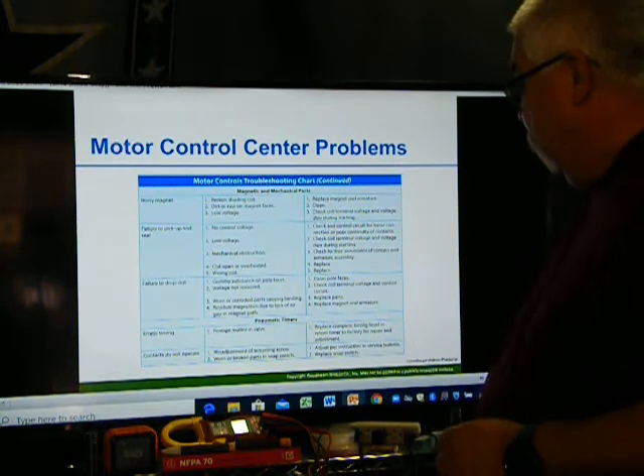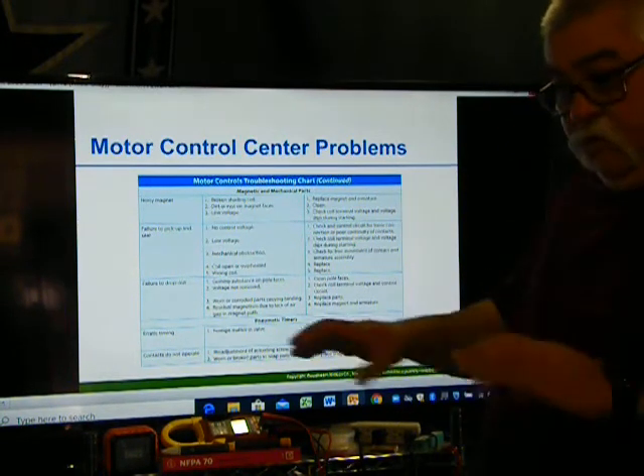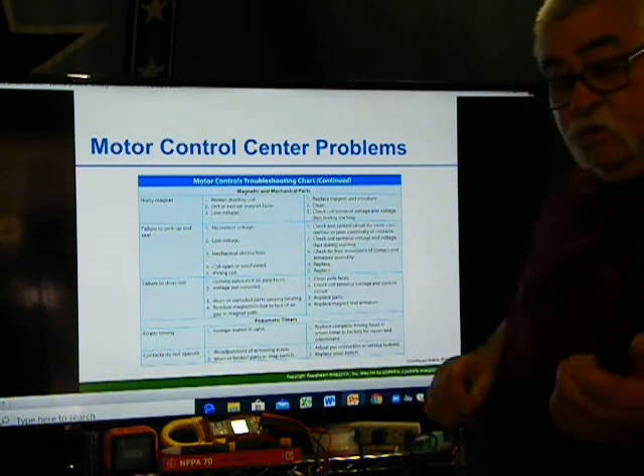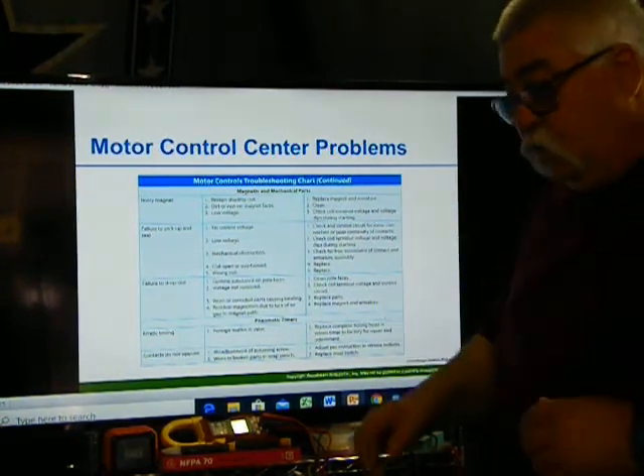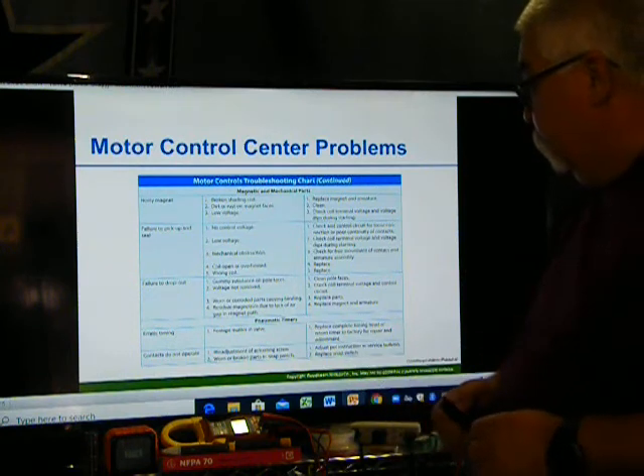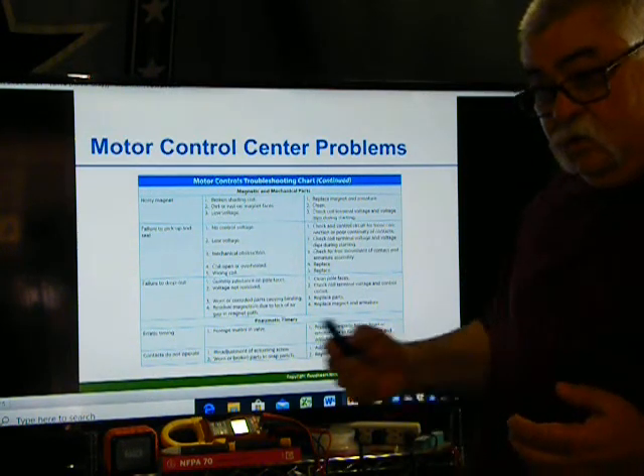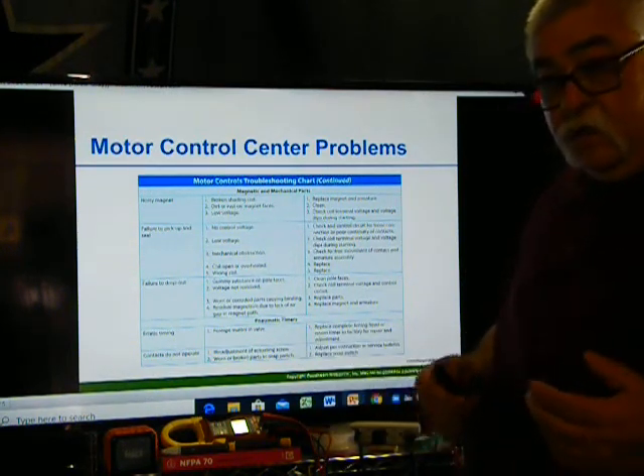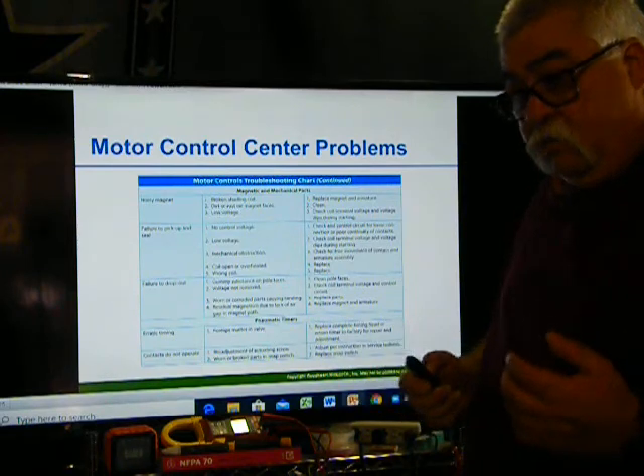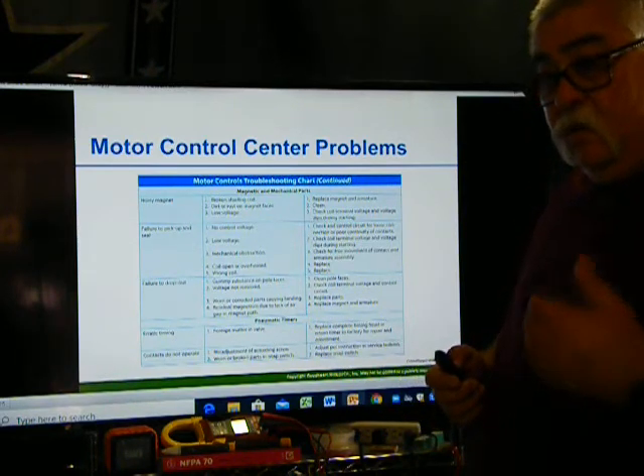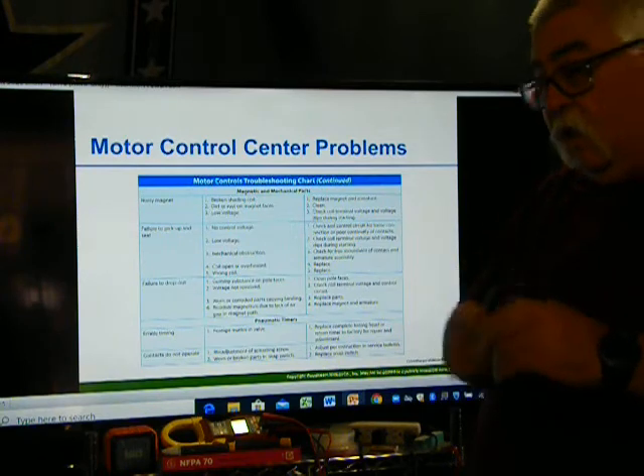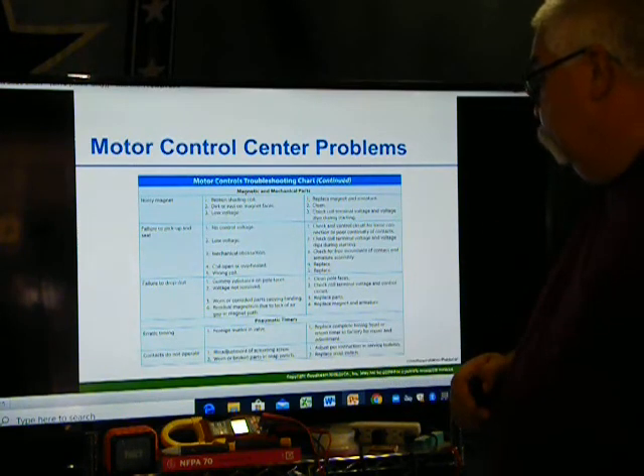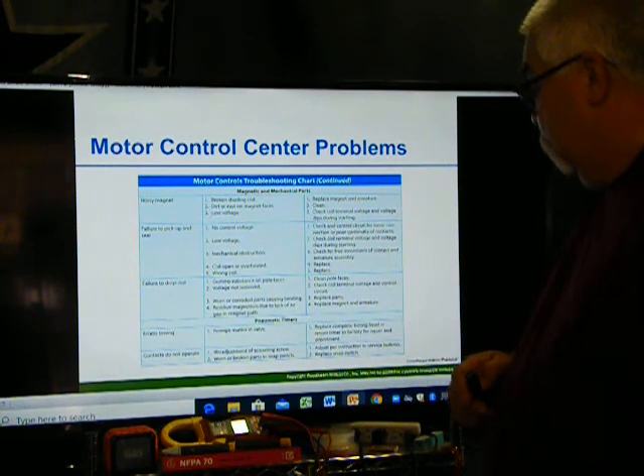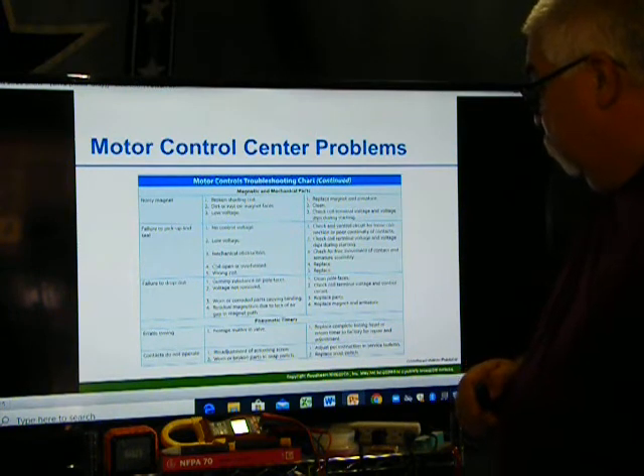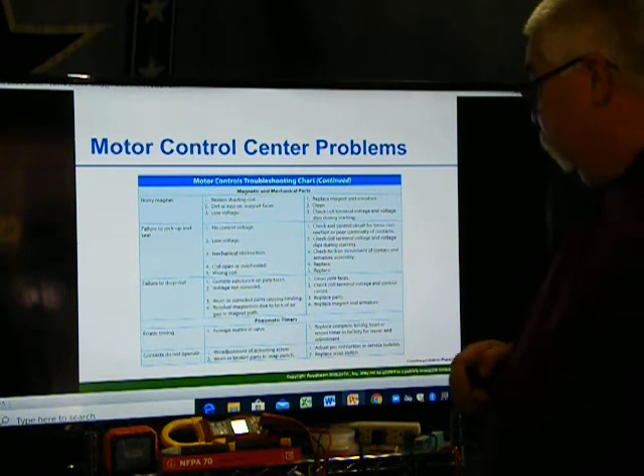Erratic timing, foreign matter in the valve. So again, if you've got something that's using pressure, it can cause problems. Make sure your pressures are right, if you're using pressure controllers that turn it on and off by air pressure or water pressure, something maybe gets stuck in there and doesn't allow it to open and close. Misadjustment of the actuating screw, worn or broken parts in the snap switch, contacts not opening and closing.